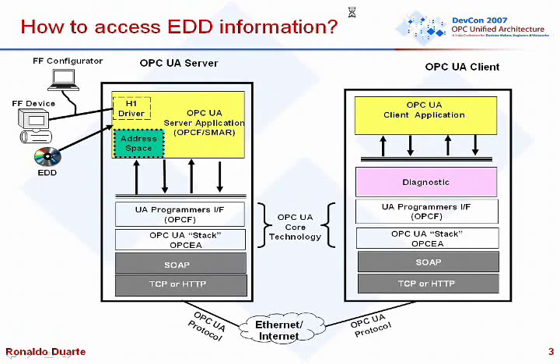Basically, to expose all the information for this demonstration, we took the OPC UA .NET reference implementation and added two components to the server. We added an H1 driver — an H1 driver is a Foundation Fieldbus network driver, so you can discover all the field devices on the network. The other component added to the reference server was the EDD server, which is the component that gives information and descriptions about the devices found on the network.